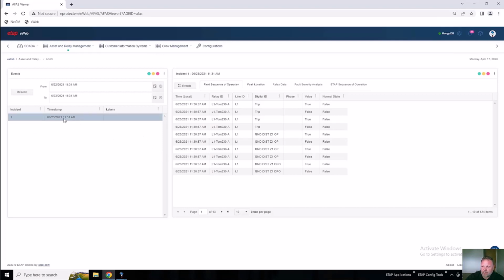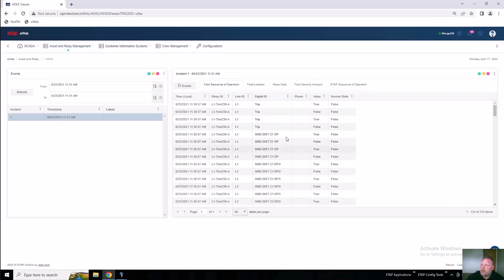For this incident, we can see that it started on the 23rd, and here we can see some of the details about that incident. First, the fault sequence of operations. Let me expand so we can see all of the digital signals that came from the disturbance records. So here you can see the time that the trip signal was detected and when it went false.